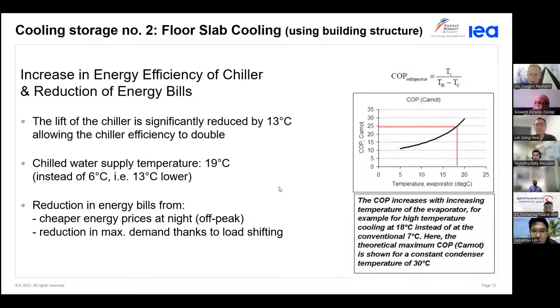So therefore you can get twice as much cooling for the same energy by doing this kind of high temperature cooling for these kind of thermally activated building systems. The other advantage is on your energy bill, because this system is running at night. So if you have a peak off-peak tariff where you can draw on the off-peak, that means you can do all your cooling for the cheaper electricity rate and also save money there.